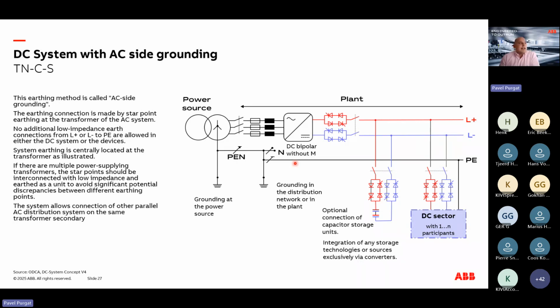This is possible as long as we have a very small DC system, and at the same time, if there are no other AC loads on the secondary side of the transformer. If there are, or if the DC system becomes large, the difficulty becomes in the currents that are circulating through your earth, and this can lead even to corrosion in the building. So this type of grounding should be reserved for the very, very small systems done in DC.